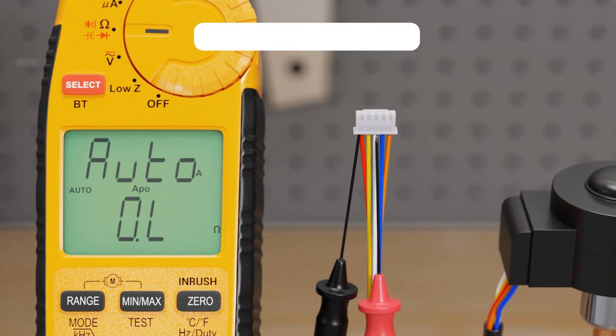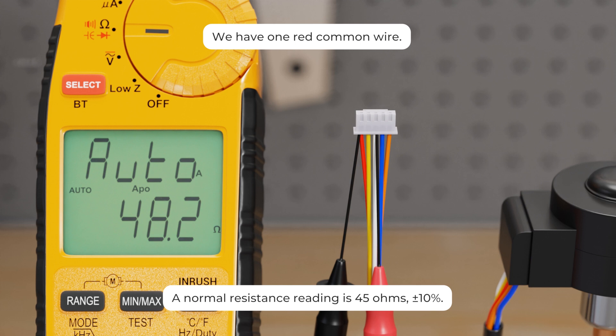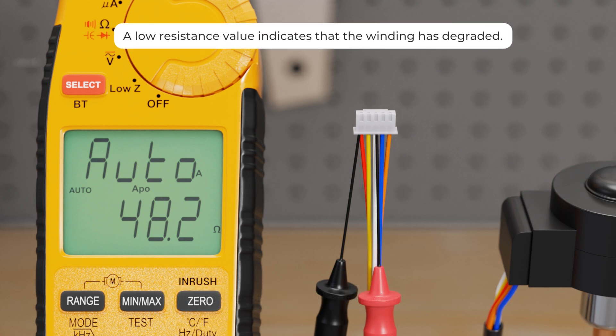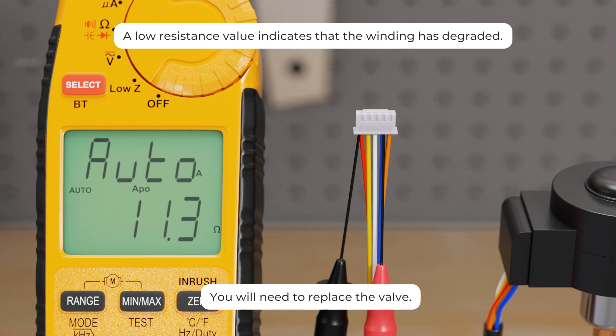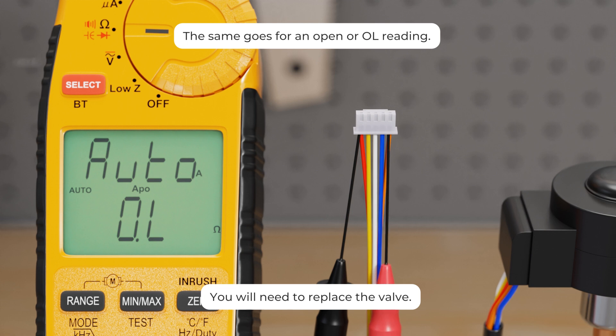In this case we have one red common wire and a normal resistance reading is 45 ohms plus or minus 10%. A low resistance value indicates that the winding has degraded. You will need to replace the valve. The same goes for an open or OL reading.